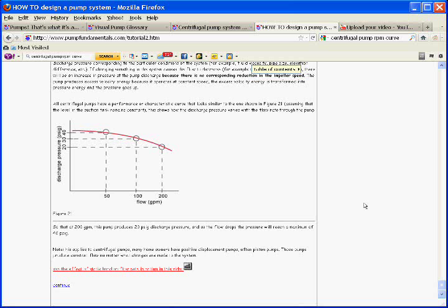If I was to all of a sudden decide I want more consumers or I want this pipe to be longer because my consumer is farther away, then yes, I will need higher pressure to satisfy those conditions. How will I get higher pressure? Well, the only way I'll be able to get higher pressure is if I change the impeller, put a bigger impeller in that pump if that's possible, or turn that impeller faster with a faster motor, for example, or if there's a variable speed drive, just increase the speed of the motor. And then yes, I will need higher pressure to get the required results from that system, which is a different system now.